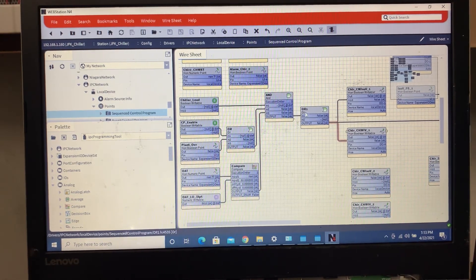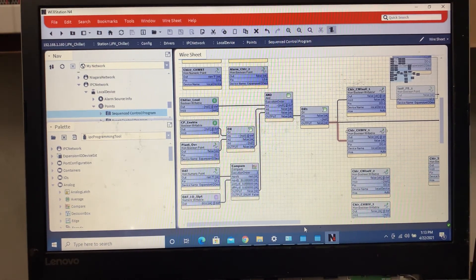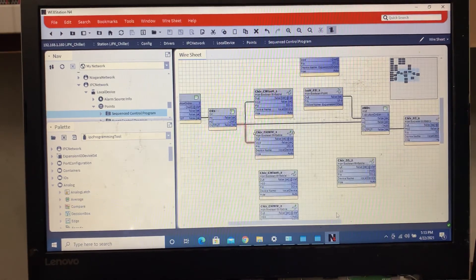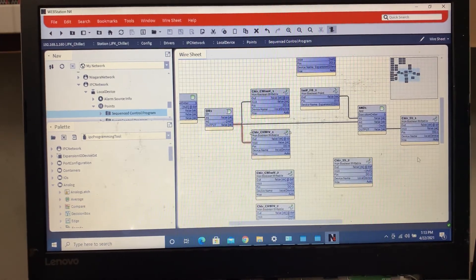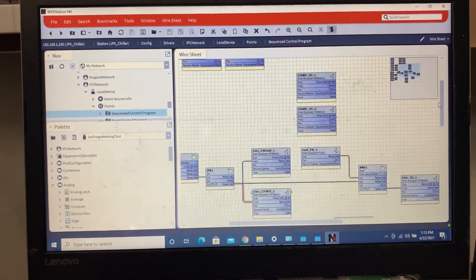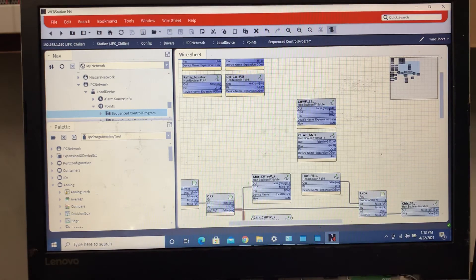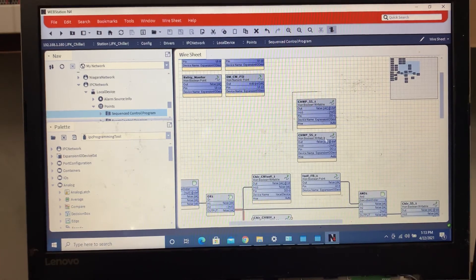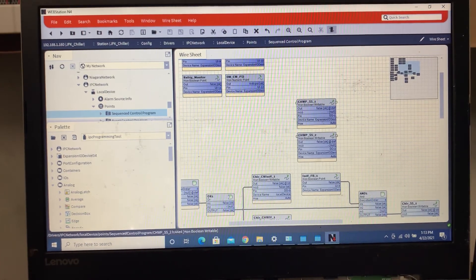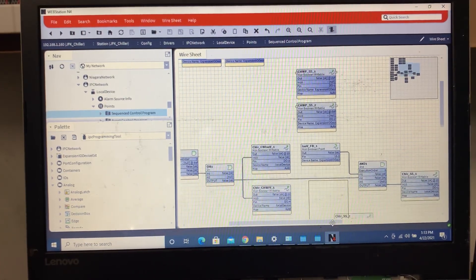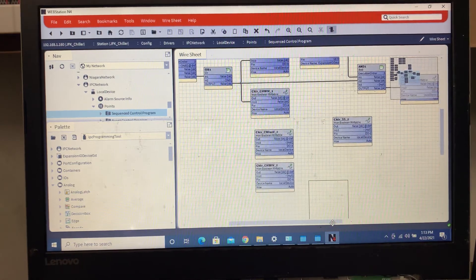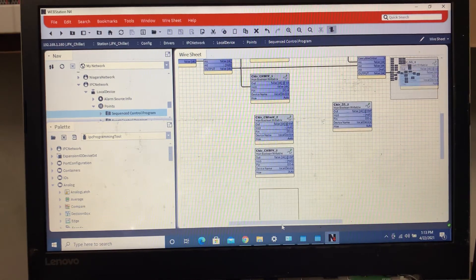What we're going to do is we're going to create lead lag logic based on a schedule, and then the same thing for the chill water pumps. Because the chill water pumps are not dedicated, and what the customer wants is they want the ability for the chill water pumps to also do their own lead lag rotation, which I'll be creating here below all this.